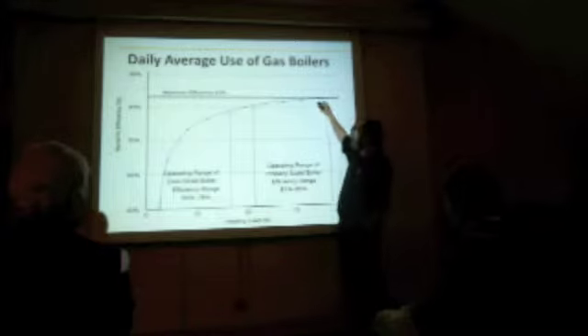And so what we find is, since the system is oversized for the demand, if you're running on average down around 20%, you're probably only running the boilers for a large part of the year somewhere between 70 and 75% efficient. So it's not terribly far away from their maximum of 80. But it is burning gas that's not needed, and if your control system can be made to stage them, which it looks like it should be able to do, that would be essentially a no-cost option.